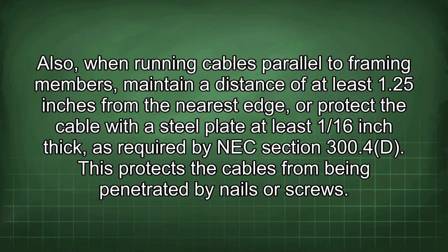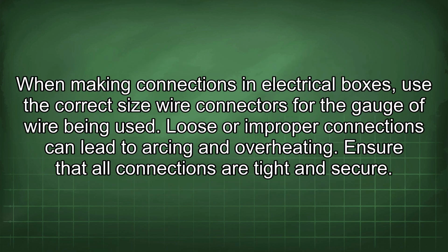Also, when running cables parallel to framing members, maintain a distance of at least 1.25 inches from the nearest edge, or protect the cable with a steel plate at least 1/16 inch thick, as required by NEC Section 300.4(D). This protects the cables from being penetrated by nails or screws. When making connections in electrical boxes, use the correct size wire connectors for the gauge of wire being used. Loose or improper connections can lead to arcing and overheating. Ensure that all connections are tight and secure.